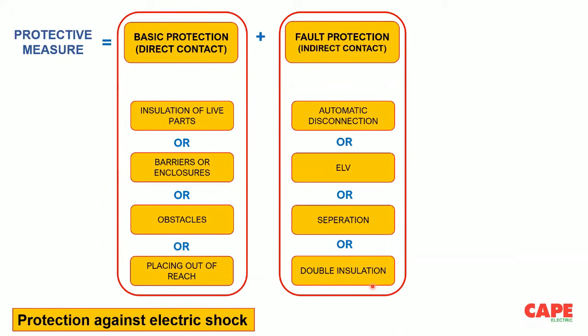Therefore, for the DC side of a solar PV installation, we are supposed to follow a system called double insulation. From the terminals of the solar PV up to the terminal of the combiner box or up to the terminal of the inverter, the entire DC electrical installation must be double insulated.